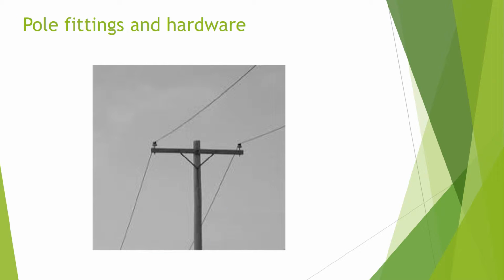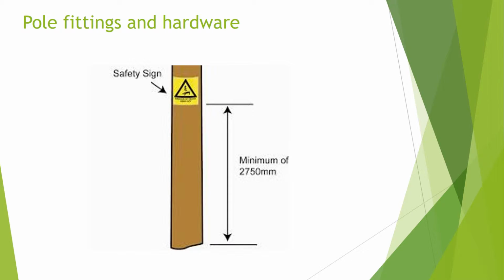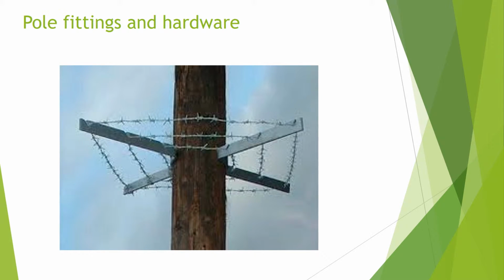Once set into position, the pole is dressed with hardware and fittings prior to the installation of conductors. As we will see, the hardware and fittings will vary on the pole type and its purpose, but all poles will have the following fitted: a galvanised steel cross-arm mounted towards the top, to which will be fitted insulators to carry conductors, a yellow danger notice, and a form of anti-climb device, usually featuring barbed wire to put off potential vandals.